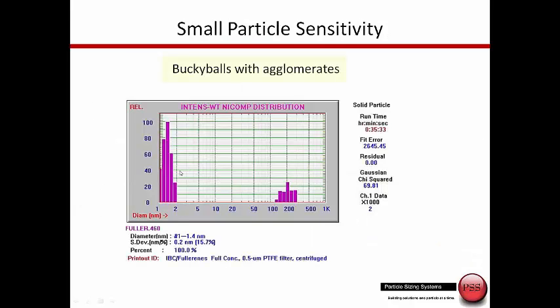This shows data from Buckminster fullerenes or buckyballs where the first peak is at 1.4 nanometers where they are expected. So we show the peak of the very small buckyballs and up here are some agglomerates at 200 nanometers. This is showing the ability to both detect very small particles and also resolve the second peak of the agglomerated sample.